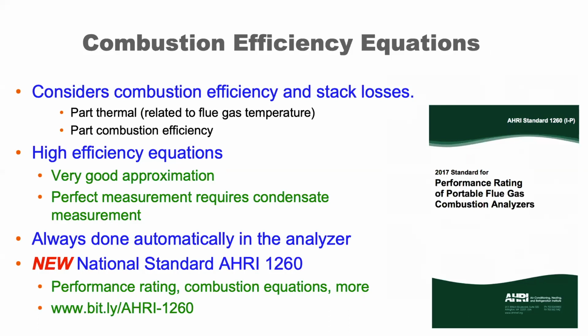Combustion efficiency equations are part of every combustion analyzer. And there's actually now a performance standard that's written by the AHRI, the Air Conditioning, Heating, Refrigeration Institute, which is a member organization of all the manufacturers that are involved in air conditioning, heating, refrigeration. I helped to start this committee a number of years ago, and the standard actually came out in 2017. And the standard for the efficiency equation considers stack losses and combustion efficiency. So part of it's due to the thermal performance, and part of it's due to actually how you create that temperature. And the high efficiency equations are also baked into the new standard.